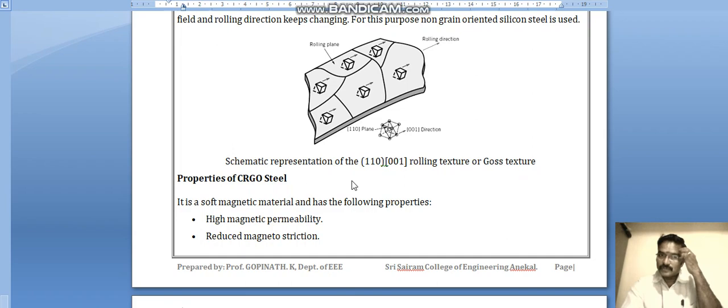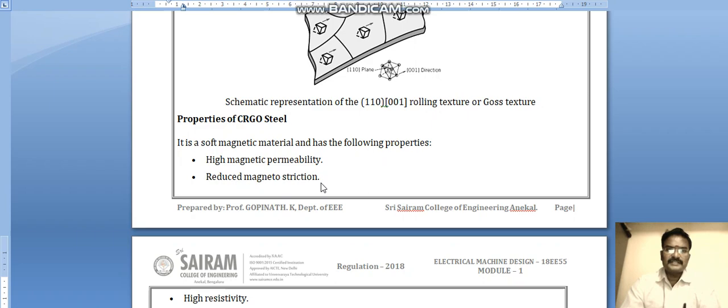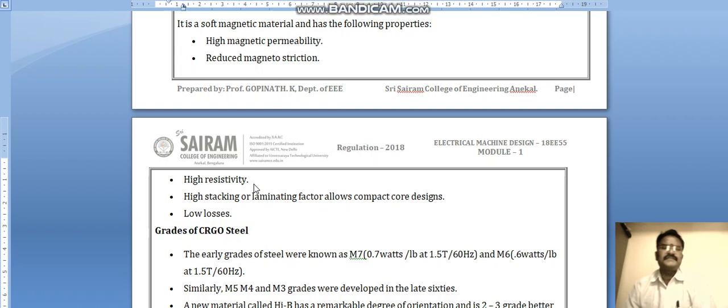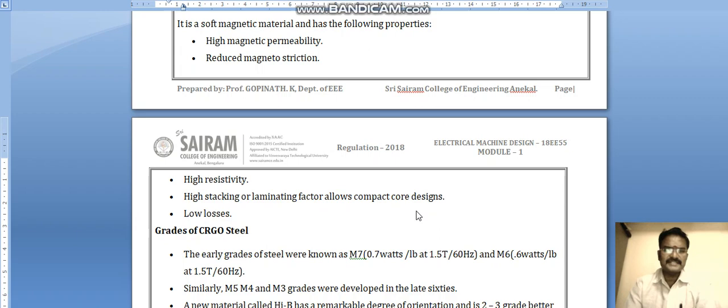Properties of CRGO cold rolled grain oriented steels include: high magnetic permeability — it becomes easily magnetized; reduced magnetostriction in transformers; high resistivity due to the CRGO manufacturing method; high stacking or laminating factor allowing compact core design with very thin laminations; and low losses overall.